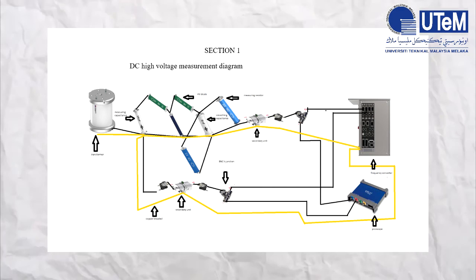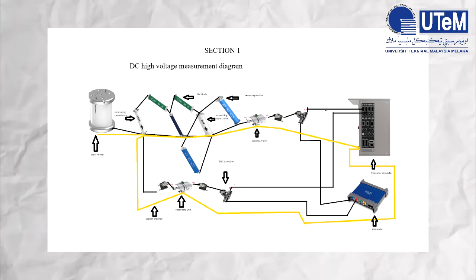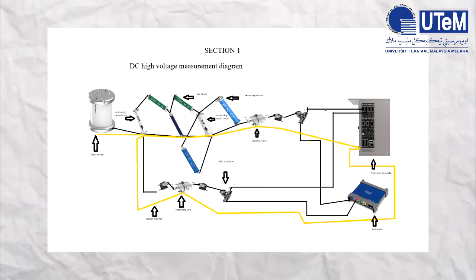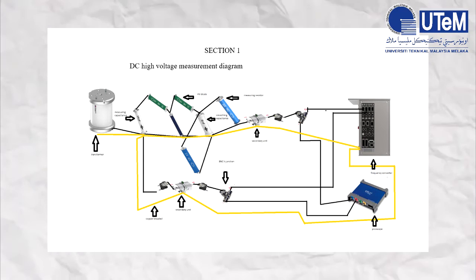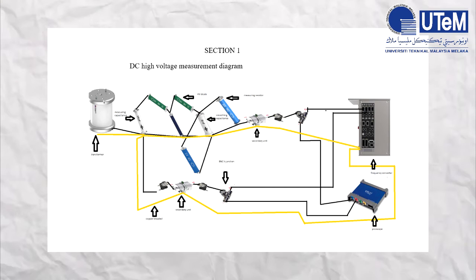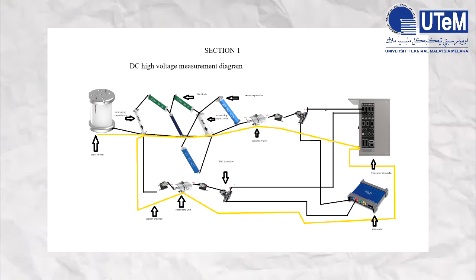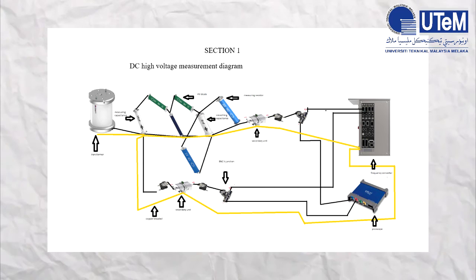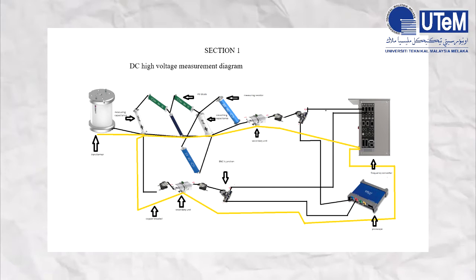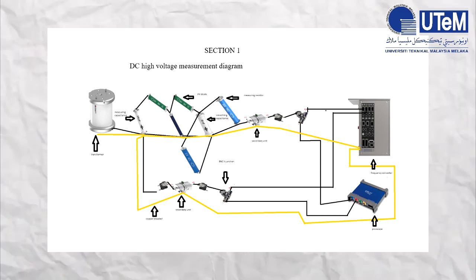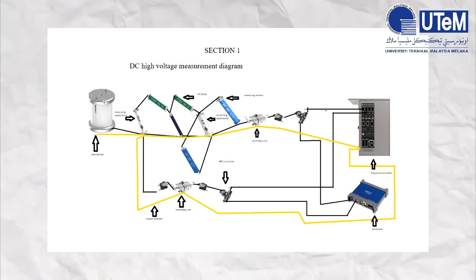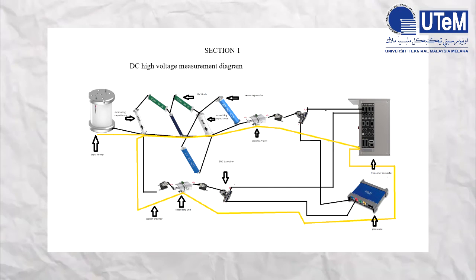The function of the rectifier is to block voltage. Each rectifier blocks 140 kV, and if there are two diodes, it will block 280 kV. The diodes are in forward bias.